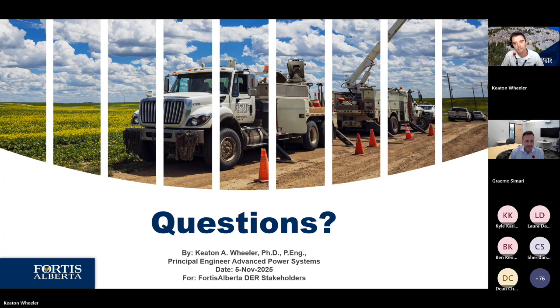Hi, this is Herman. Just a quick question for you. As most of the generation units, the gensets, are not certified, we heard that CAT may be the only one that is certified. Please confirm if they are. Anyway, to my knowledge the other brands are not certified. So it looks like we need an IEEE 1547 certified reviewer to review our design to make sure we comply with IEEE 1547. My question is, if we have certified IEEE reviewers sign off on the design, should we be concerned that Fortis may later review it and say it doesn't comply? Or if our documents are signed by the reviewer, does that mean we're good to go?